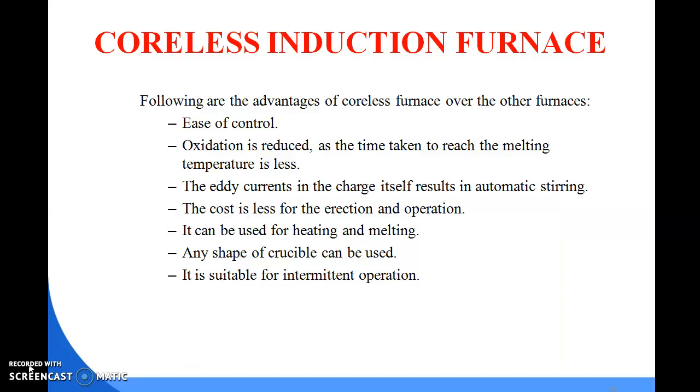Following are the advantages of the coreless furnace over the other furnaces. The ease of control. Oxidation is reduced as the time taken to reach the melting temperature is less. The eddy current in the charge itself results in automatic stirring. The cost is less for erection and operation. It can be used for heating and melting. Any shape of crucible can be used. It is suitable for intermittent operation.